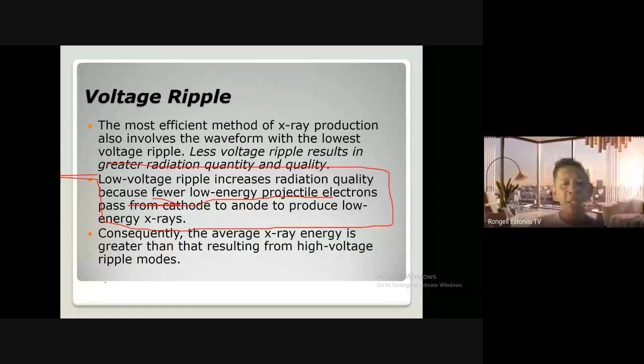Less voltage ripple results in greater radiation quantity and quality. Low voltage ripple increases radiation quality because fewer low energy projectile electrons pass from cathode to produce low energy X-rays. Consequently, the average X-ray energy is greater than that resulting from high voltage ripple modes.